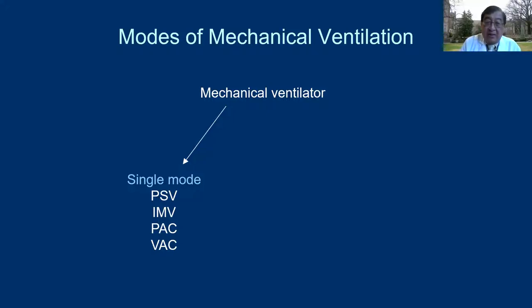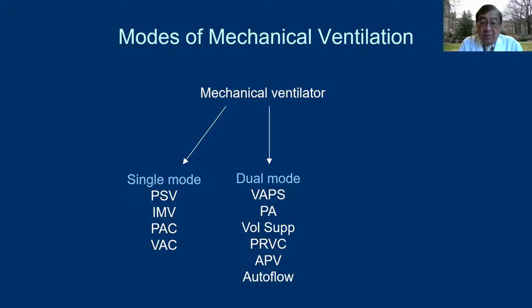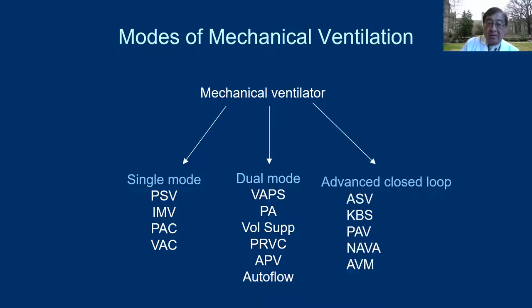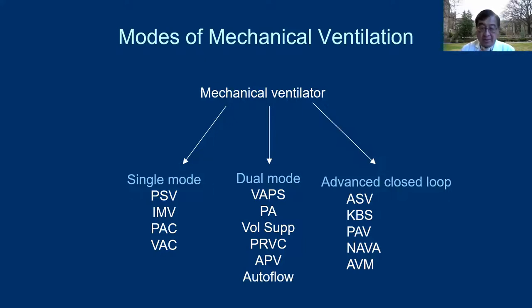Then there is the so-called dual mode — these are the VAPS mode, pressure augmentation or PA, volume support, and pressure regulated volume control (PRVC), which is pretty popular. It's called dual mode because there is a feedback loop. Most of the time tidal volume is used as a feedback parameter to maintain a minimum tidal volume. Then there's more complicated advanced closed-loop modes — adaptive support ventilation (ASV), knowledge-based systems (KBS), proportional assist, NAVA, and the adaptive ventilation mode (AVM).